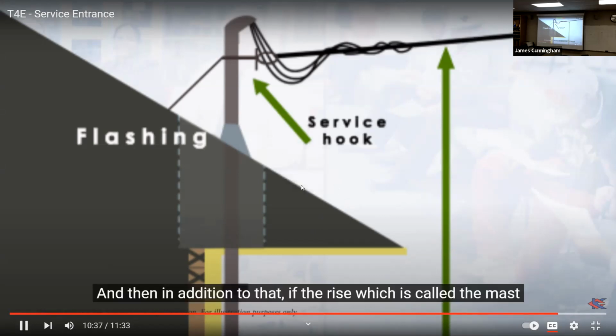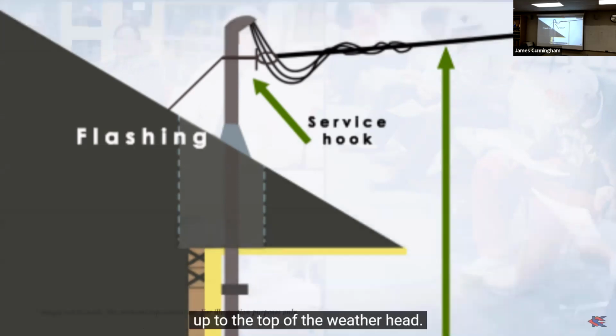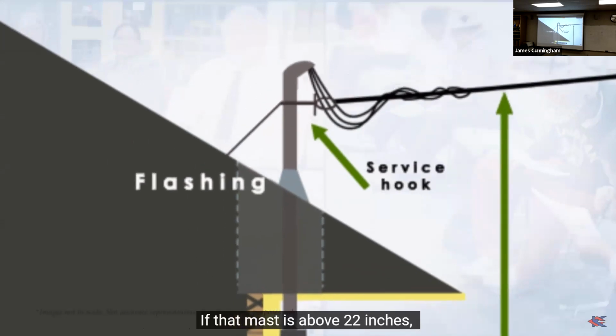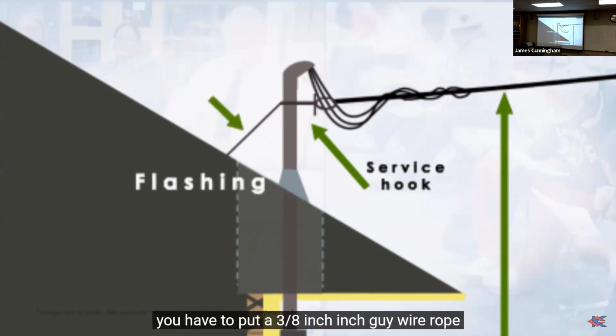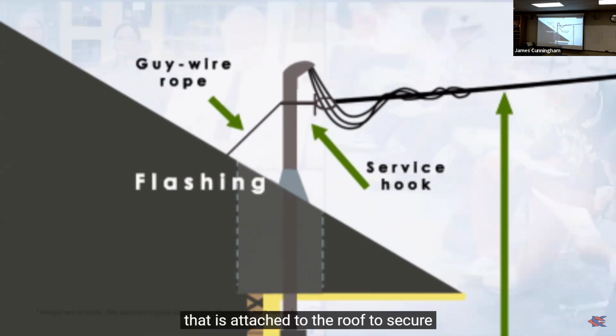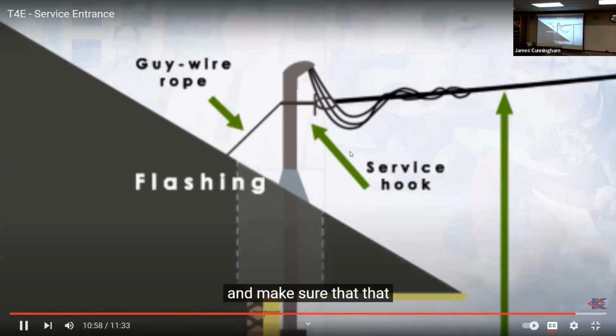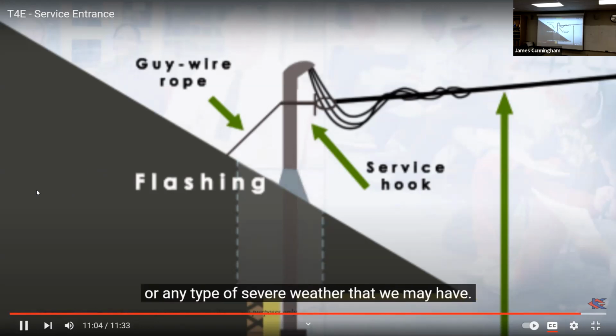Then in addition to that, the rise, which is called the mast, is the portion that comes from the roof line up to the top of the weatherhead. If that mast is above 22 inches, you have to put a 3/8 guy wire rope that is attached to the roof to make sure that mast has support. It's not a rope, it's a steel cable, so don't get confused when he says rope. It's there in the event of high winds or any type of severe weather that we may have.